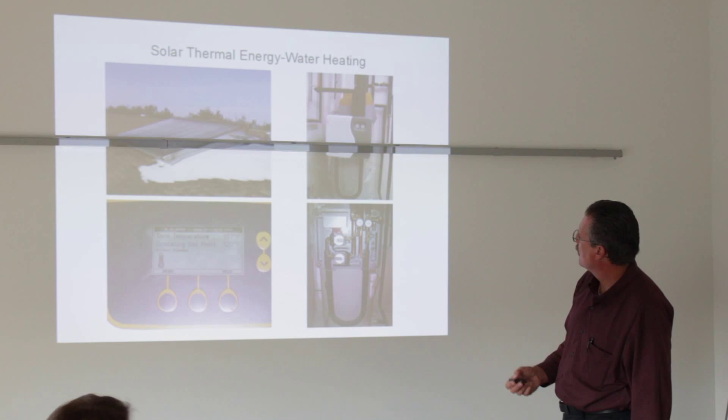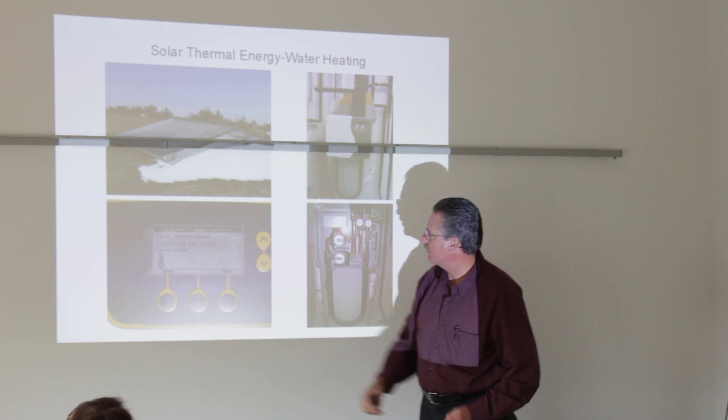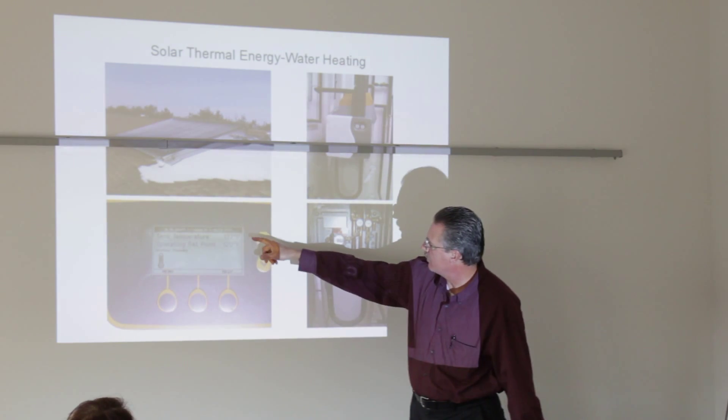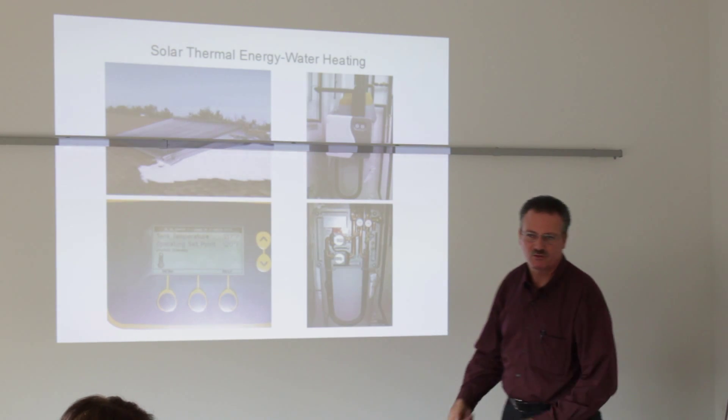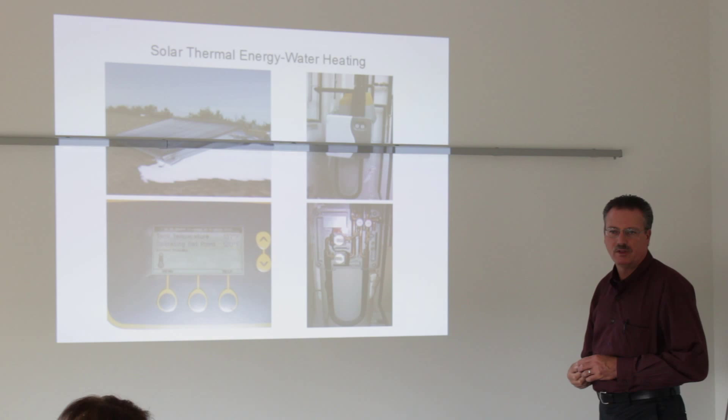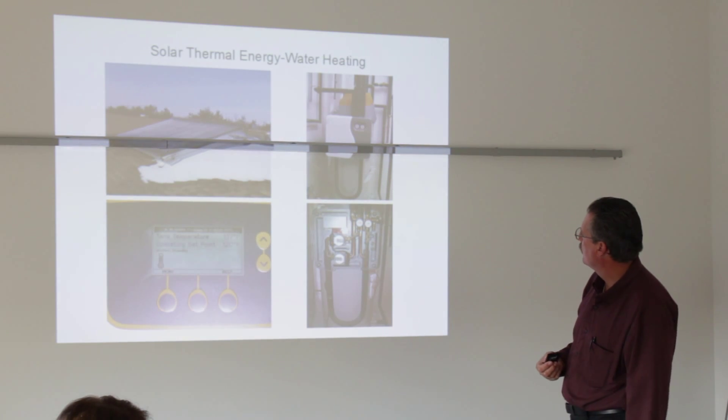And this is just an example of a unit that we did down in Shelbyville. I wanted you to see the snow and the frost on the collectors. And then notice what the tank temperature is, 137 degrees. The set point on the tank is 120, so we're already 17 degrees above set point. So there's quite a bit of excess heat there, which can be drawn off during the day.